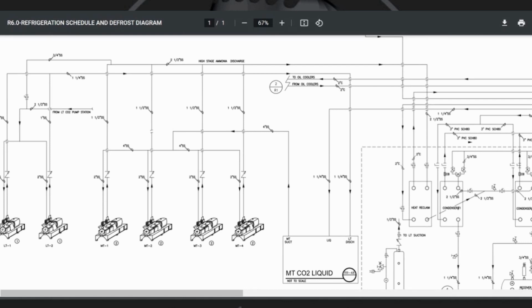Now with a DMCS, we might do a lot better because we maybe wouldn't have to go transcritical. But we're very concerned about the energy, and we are very concerned about the high pressures, our technicians working on pressures that exceed 800 pounds. On this system, the highest pressure they see is about 450 on the medium temp liquid overfeed. And when you get up into the 900 pound pressure, we're very concerned about valve failures and ruptures, and maybe it's unfounded. I know there's 600 or 700 of these things installed in the United States, or maybe thousands by now, but we just haven't gotten to the point where we're comfortable with it.